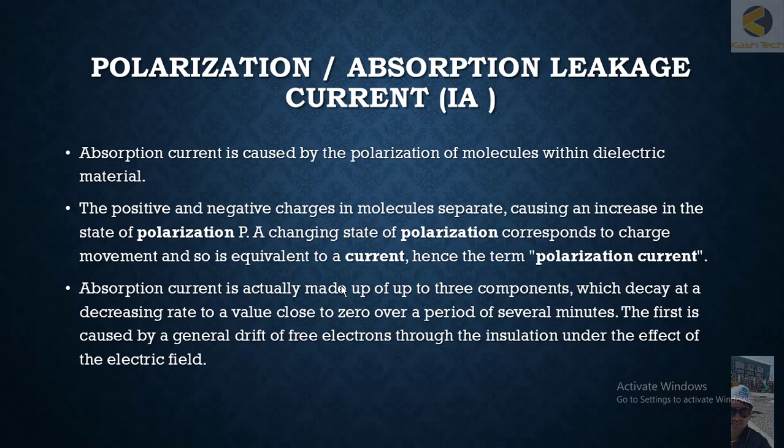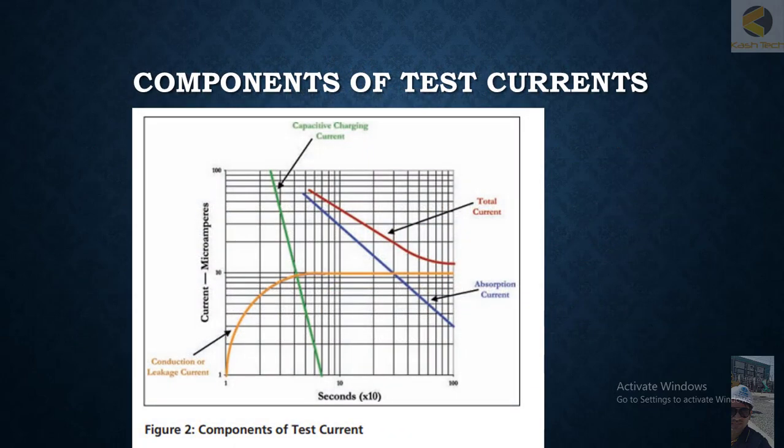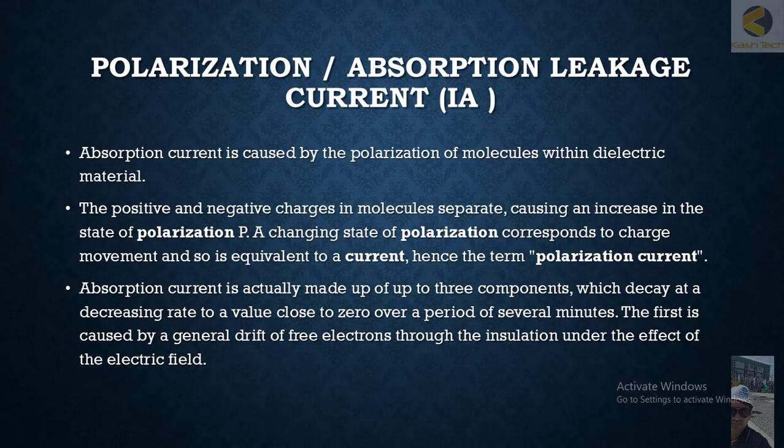Absorption current is actually made up of three components, which decay at a decreasing rate to a value close to zero over a period of several minutes. The first component is caused by the general drift of free electrons through the insulation under the effect of the electric field. The remaining two components will be discussed later in detail.